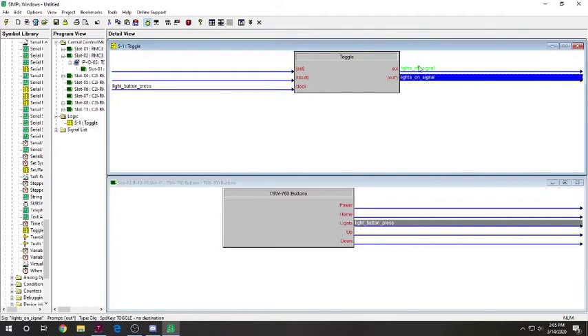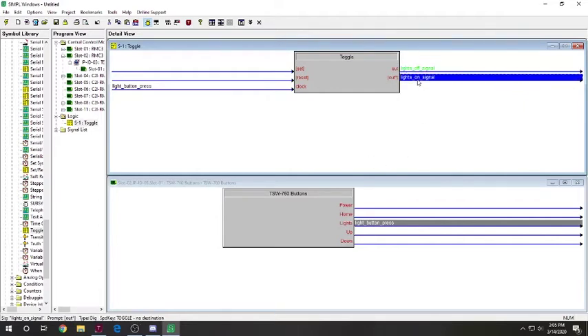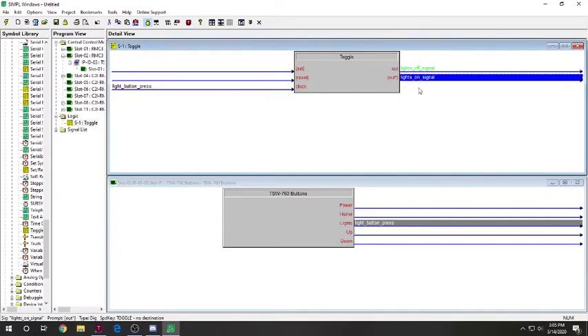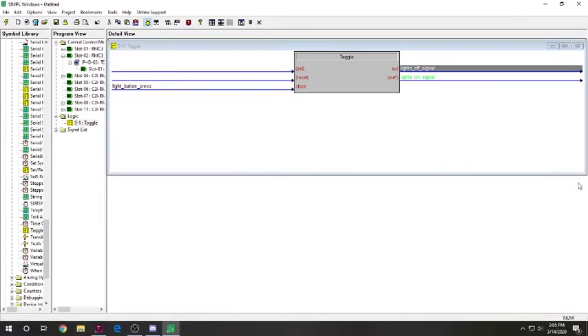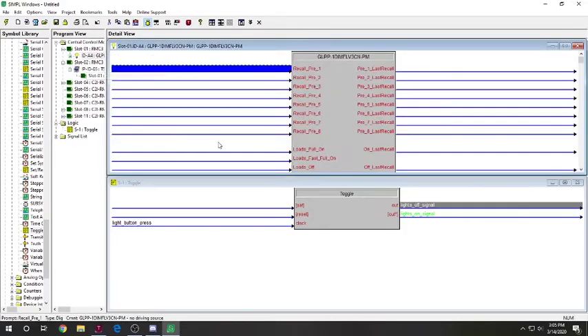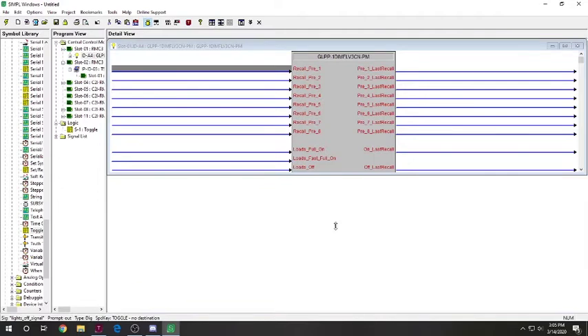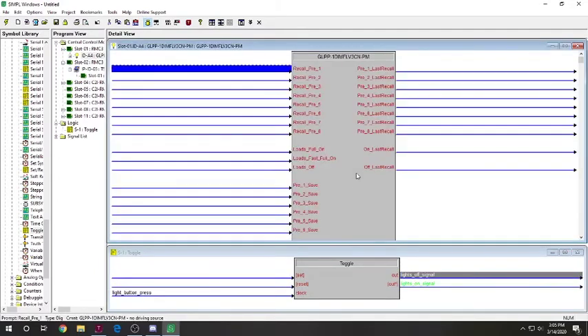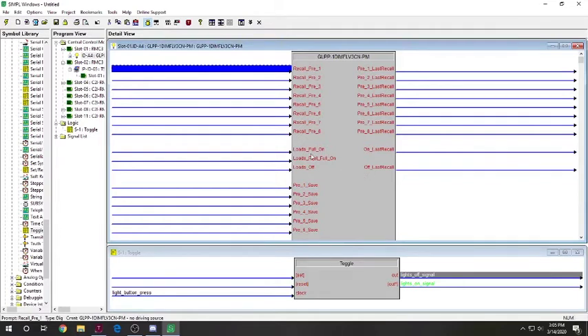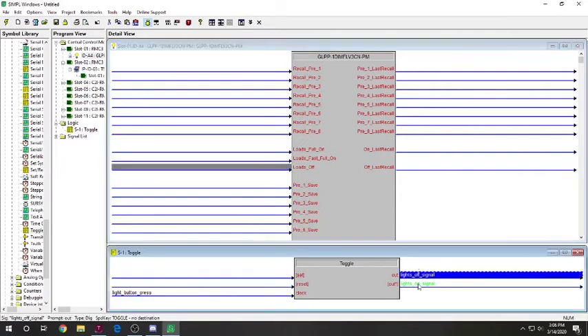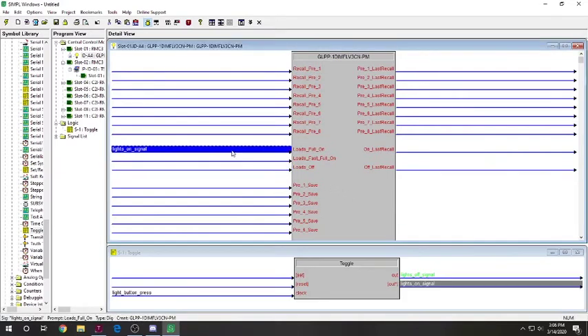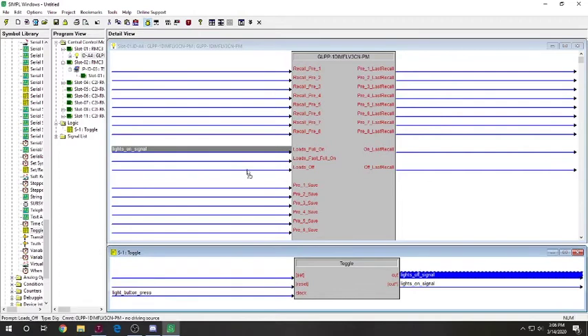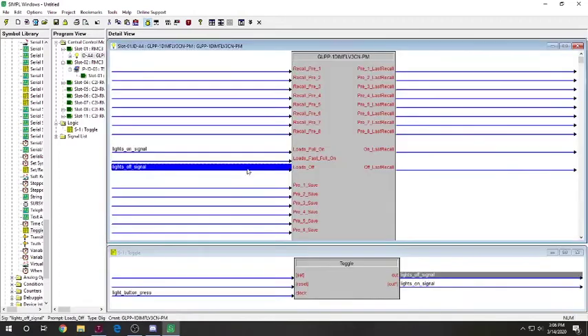Now, theoretically, we could have a light on and off switch. And then have a toggle switch. Now, you don't really need both of them at the same time. So, we're just going to stick with the toggle. So, this output, this one is going to be light off signal. And then this one is going to be light on signal. So, the reason we put the off on top and the lights on bottom is because this one is going to default to being on when the processor is starting. So, we want the lights to start off when the processor is on.